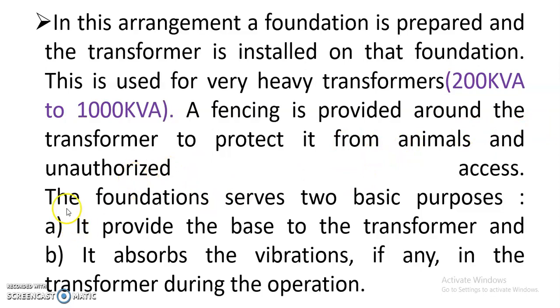So the next point is the foundation serves two basic purposes. The main purpose is to provide the base to the transformer, and the second important thing is that it absorbs the vibration, if any, in the transformer during operation. If vibration takes place in a transformer, that foundation will absorb this vibration. So these are the two advantages of your plinth mounted substations.